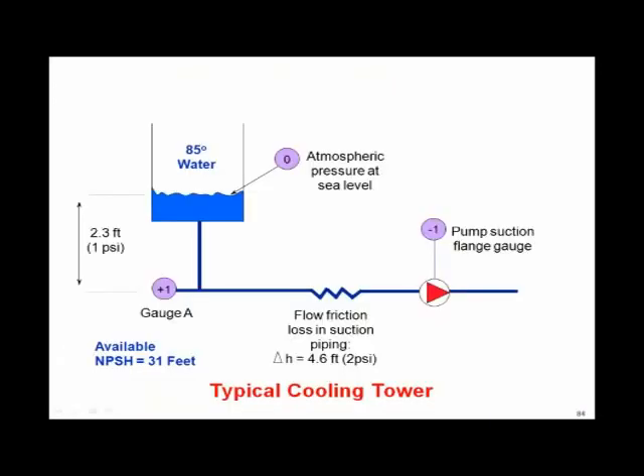Here's a typical example of what I was trying to give you. Look at a cooling tower at Myrtle Beach. And we're just going to look a little bit at NPSH. I wish we had an hour on that, but we don't. We got another YouTube, by the way, if you want to look at NPSH, go on and take a look at it. But here's a cooling tower at Myrtle Beach, no hurricane, 0 PSIG, 85-degree water. And let's just look at a typical piping of a tower. Now, let's assume that the tower is elevated 2.3 feet above the center line of the pump, okay? Let's assume there's 4.6 feet of pressure drop between the tower and the suction of the pump.